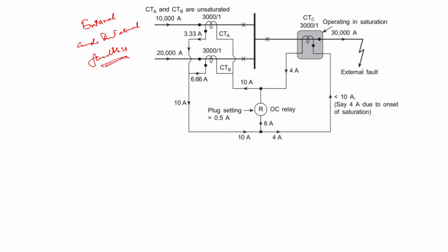Now, in the previous discussion, we have assumed that CTs are ideal. When the CT primary current or the burden on it is within the design limits, the CT can indeed be assumed to be more or less ideal. However, if the primary current goes on increasing and exceeds the design value, or the CT burden, which is the output of the CT, becomes excessive, the CT no longer behaves like an ideal CT, it becomes saturated.